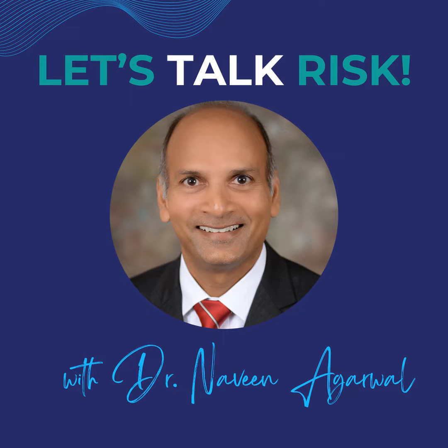Yeah, sure. So one thing that's always tricky in any design work you do is the reliability numbers that are associated generally with design verification testing. It's always a fun discussion on what the reliability number should be. Oftentimes you'll see companies have a matrix that says, if your risk for this design verification test is high, then you want to use 99%. If it's medium, 95%. If it's low, 90 or something like that. So generally there's a sliding scale. The riskier the product is, the higher reliability numbers you should use for testing to make sure that the product's going to function correctly.